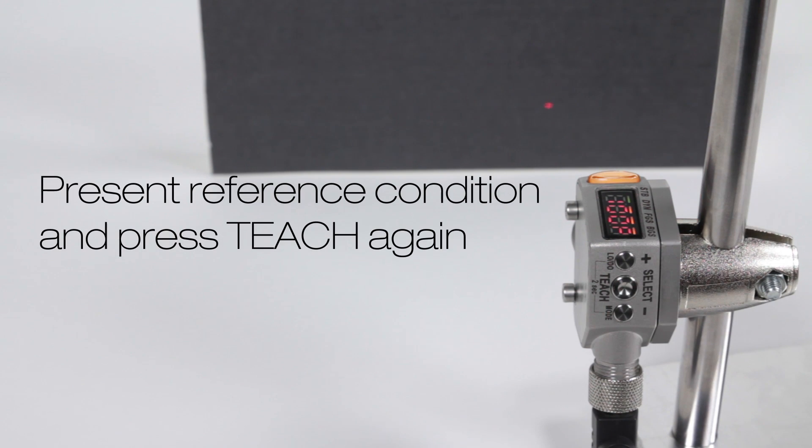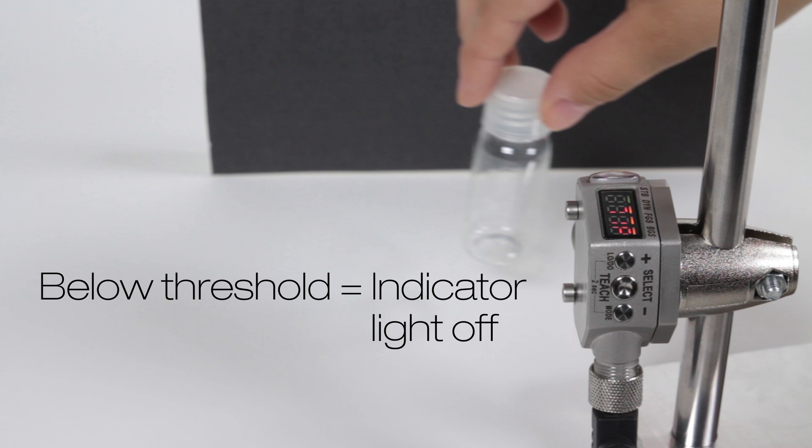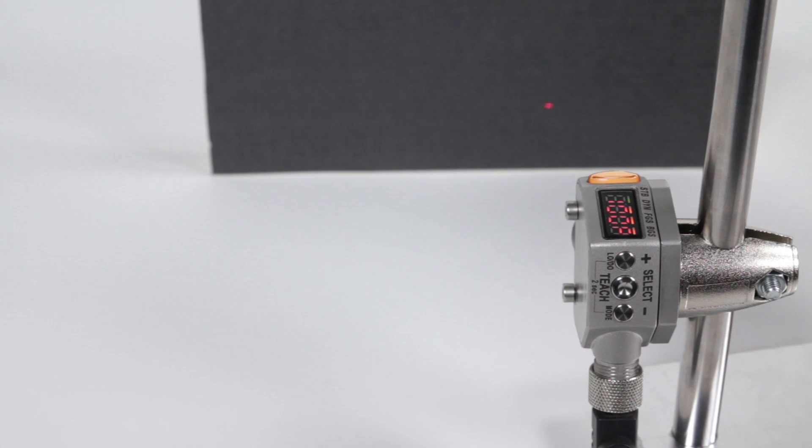Present a reference condition and click the button again to teach the reference condition. The sensor learns this as a 100% match condition and will look for changes in distance, intensity or a second reflection condition. The Q4X can reliably detect clear or transparent objects including vials, films and bottles.